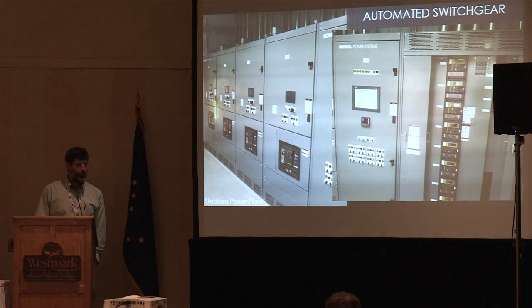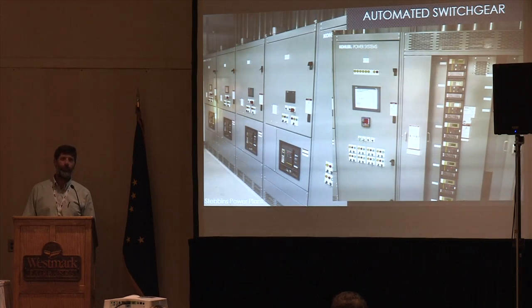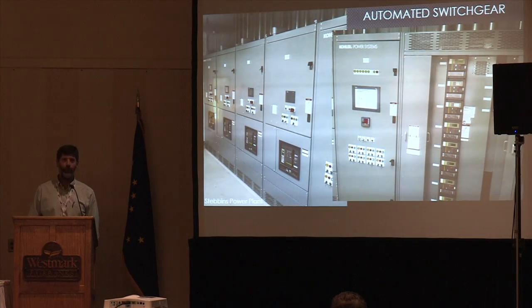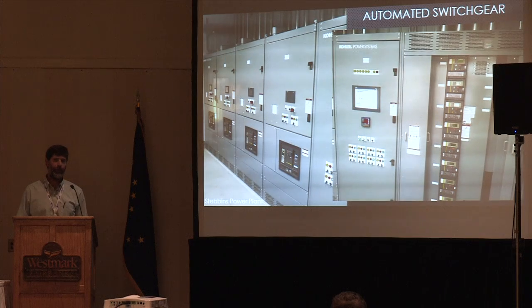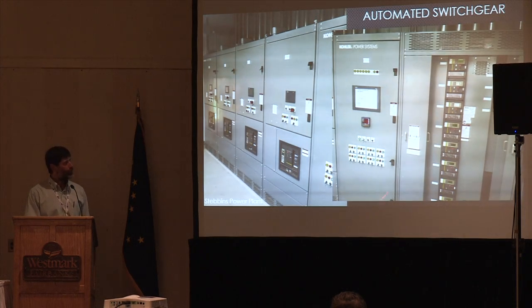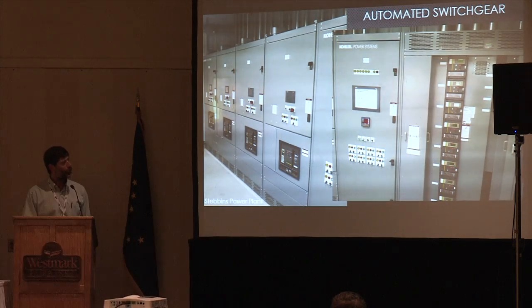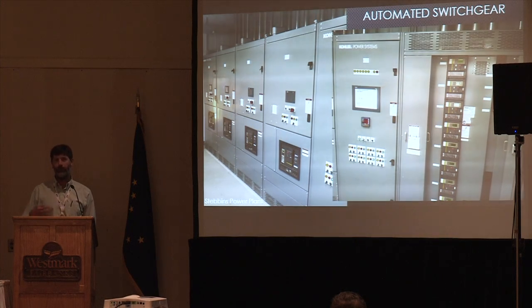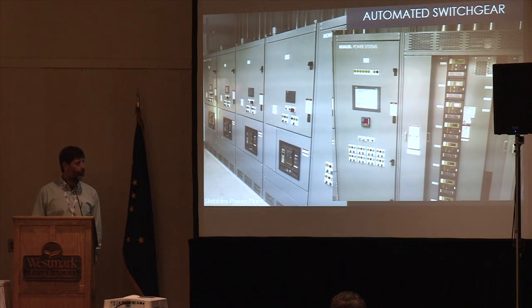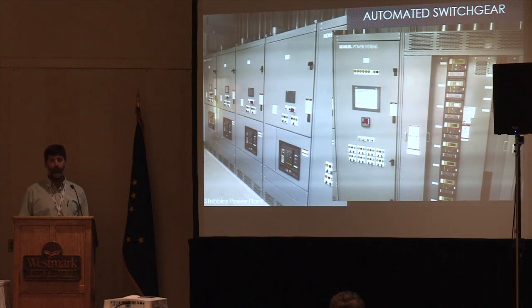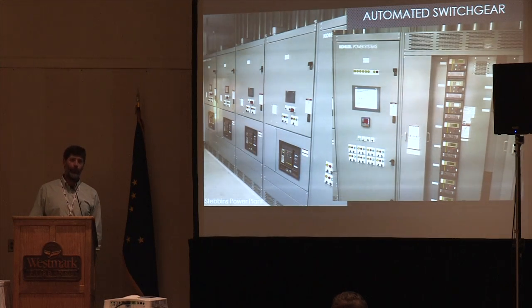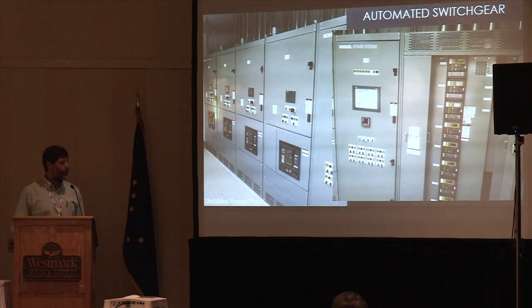AVEC has a policy on our distribution system. In pretty remote villages we do everything de-energized, so we place a lot of emphasis on sectionalizing our loads out to the village. We've got a lot of breakers inside our plants so you can turn off different phases, different sections of town to go out and do some work. It's also beneficial that if there's a fault on the line, it'll only trip one section of town. You've got time to go and fix that, and you don't lose the whole village.